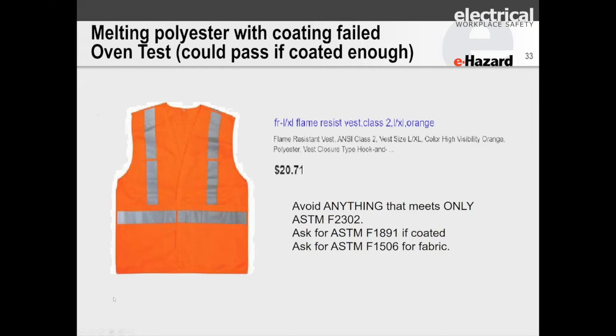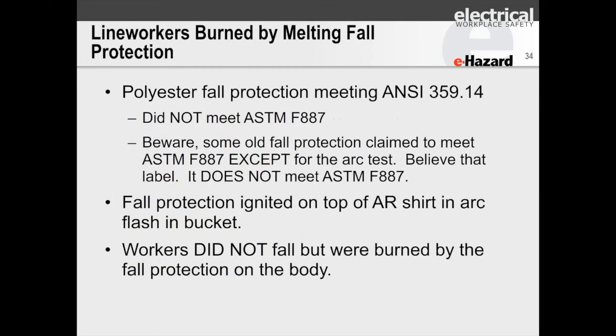This melting vest here, past 2302, they can say it's flame resistant, but it doesn't meet any flame resistant test except 2 small scale tests that aren't predictive of burns. And this material is a rainwear type material, and it burns like crazy in an arc flash or a flash fire. So I encourage you to use 1891 or 1506. Those are the only 2 acceptable standards in US, and IEC has a couple of standards. Those are all listed in the Z462 standard or the NFPA 70E standard. Use the right standards. Feel free to contact us. We'll help you find the right standards, but we don't sell PPE or anything.